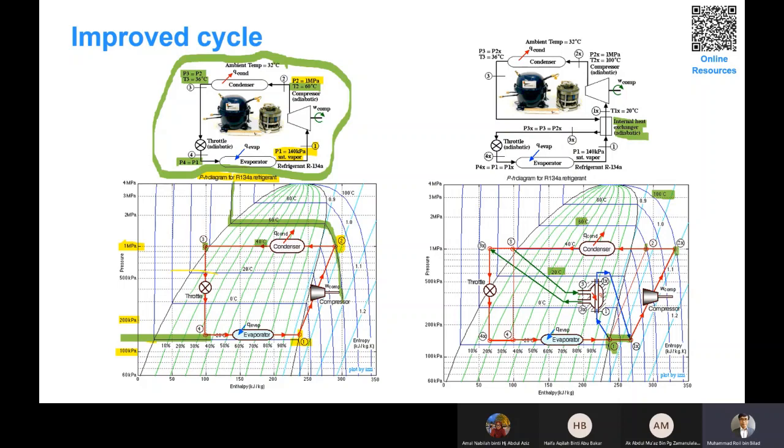And we bring it to the condenser. In the condenser, before it was subcooled liquid at 36 degrees Celsius, given here. And now, thanks to the heat exchanger, we bring it down further to the left, to the point of 3x. The temperature is cooled down to somewhere between 20 and 0, not the middle, so not 10, probably around 12 degrees Celsius at 3x.